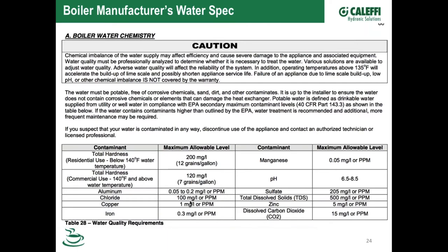Why we're concerned about the dissolved gases, especially oxygen, is that's what makes water aggressive for corrosion. And our opinion is, if you use a good component like a Caleffi air separator, you're going to pull all those dissolved gases, both the air and the dissolved CO2 and oxygen, out of there just by running through a good air separation device, like a micro bubble type device.